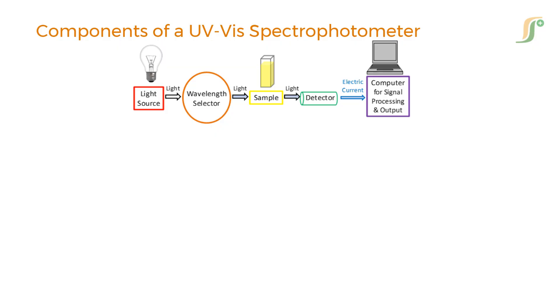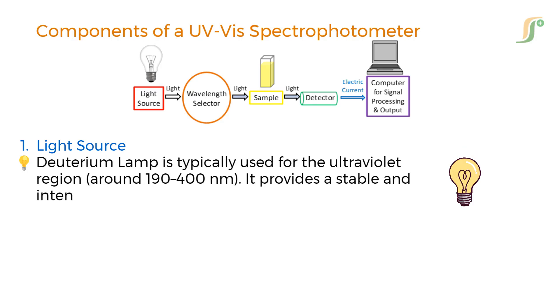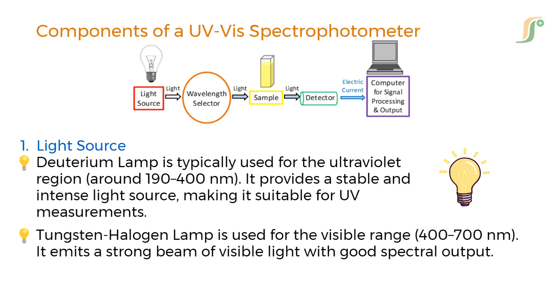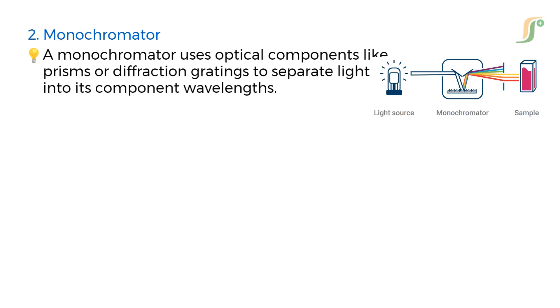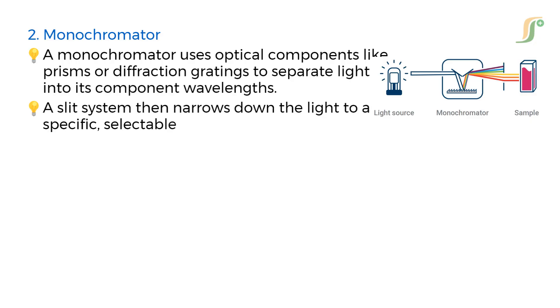A UV-visible spectrophotometer is a sophisticated yet easy-to-understand analytical instrument made up of several essential components. The light source includes a deuterium lamp, typically used for the ultraviolet region around 190 to 400 nanometers, which provides a stable and intense light source suitable for UV measurements. A tungsten halogen lamp is used for the visible range, 400 to 700 nanometers, emitting a strong beam of visible light with good spectral output. The monochromator uses optical components like prisms or diffraction gratings to separate light into its component wavelengths, and a slit system then narrows down the light to a specific, selectable wavelength which is sent to the sample.